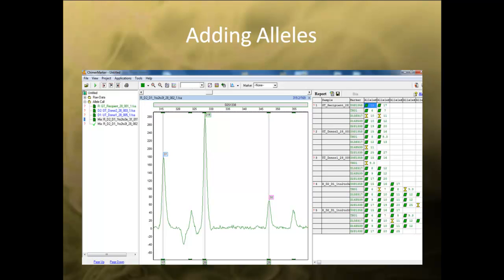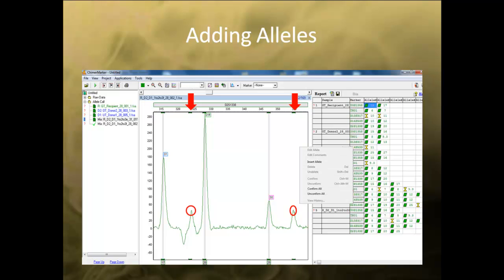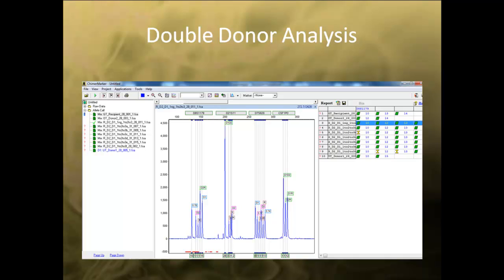Before moving on to Chimerism Analysis, you should review your data to make sure all desired peaks are called. In this example, there are two empty bins from the Chimer Typing Panel because these alleles did not pass the minimum detection threshold. However, you can manually include the peak by right-clicking at the very tip of the peak to ensure accurate height and area measurement, and selecting Insert Allele. Using this method, you can include or exclude any allele from the chimerism calculations. All alleles will have an identification after the analysis finishes: D1 stands for Donor 1, D2 for Donor 2, and R for Recipient. Any shared allele will be indicated by each of the identifiers just mentioned.